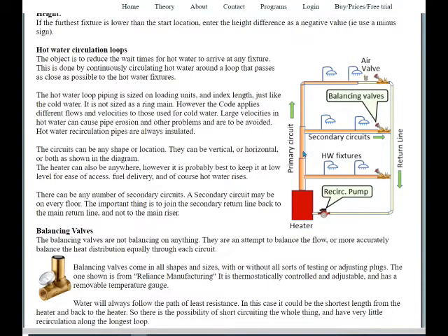So all the pipes that we see in this loop are the ones that we'll add in that table further up. But sometimes we don't know whether this is the worst case, that one, or maybe this one. It depends on what fixtures are on it and what the pipe size is. But to work out the pump head, we need to know the worst case, because that'll be the highest head. So let's say the longest one. It's normally the worst case anyway. So we always try with that one first.